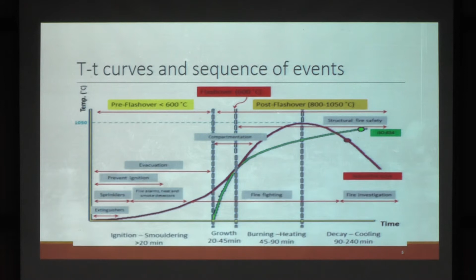And this green curve is the so-called standard fire curve, or the ISO 834 curve. This is typically used in design. So when we say that a structural member or a beam or a column is 30 minutes fire rated, what we mean is that given 30 minutes of this exposure, it will remain safe. That's the idea. And most of the operations, like use of extinguishers or action of sprinklers or smoke detectors, etc., will happen in the pre-flashover region, which is the smoldering stage. So the sprinklers are a fire control mechanism, not really a fire extinguishing mechanism.